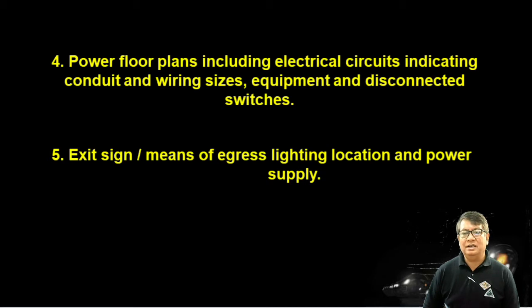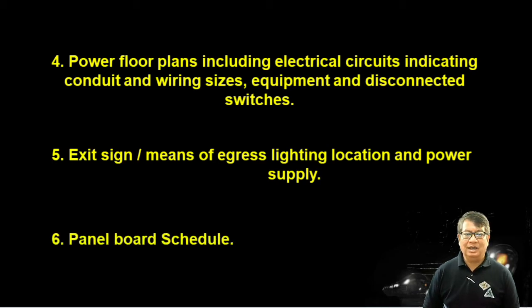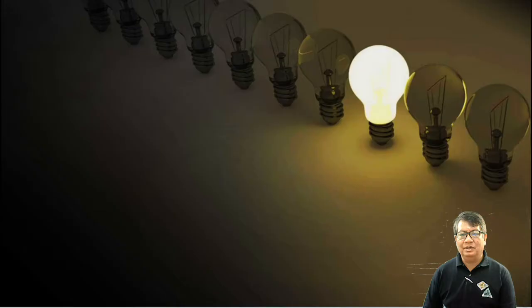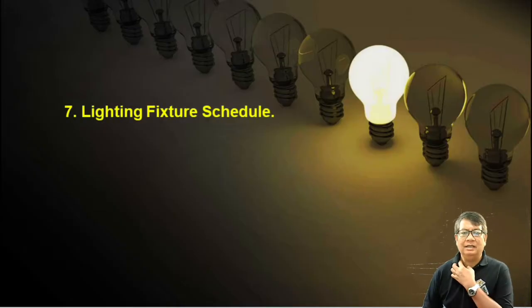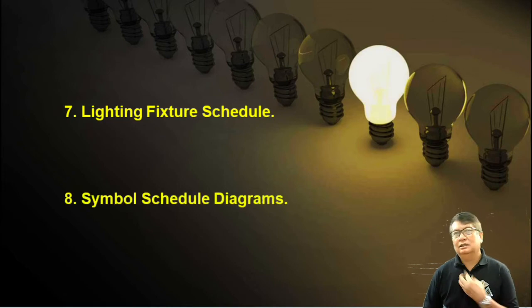Okay, so exit sign, means of egress, lighting, location, and power supply. So we need to indicate also the signages, especially for entrance, exit, fire exit, comfort rooms, and any other stairs, elevators, so on and so forth. So any other signages, we have to find or locate. Okay. So we have also some other egress, lighting, location, and power supply, kung saan po nakalagay yung power supply natin. And it will also indicate the panel board schedule. Okay, number 7, lighting fixture schedule, or tinatawag natin po itong schedule of loads, no? So we have the symbol schedule diagrams.